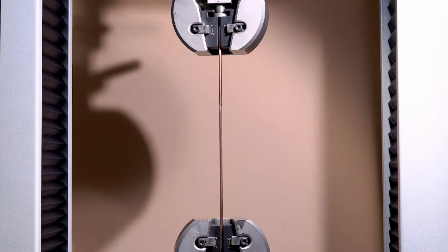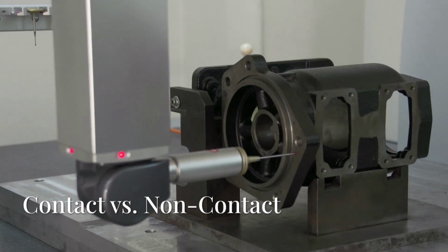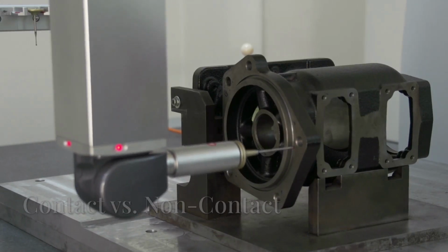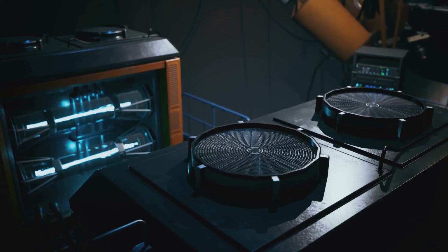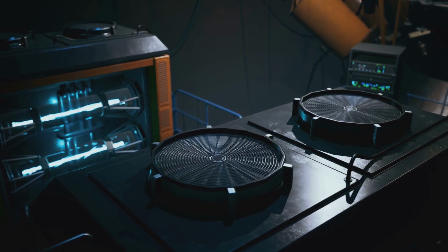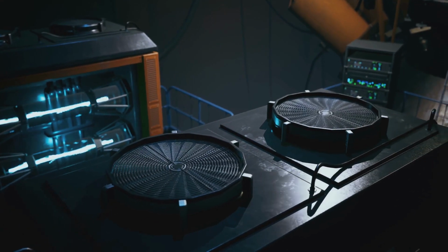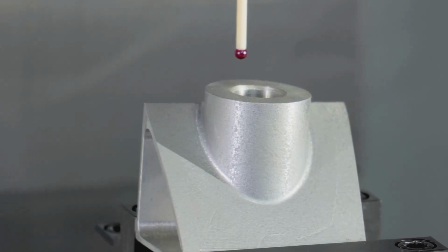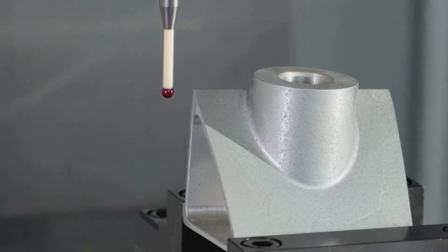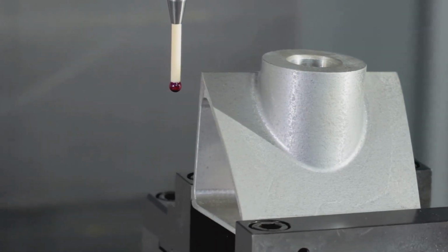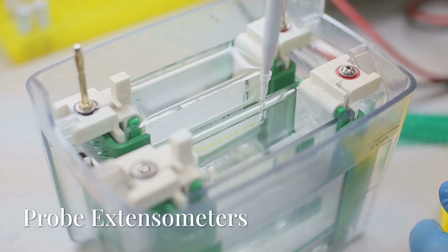Very thin specimens, such as foils, may be sensitive to clamping forces, while very small wire specimens do not provide enough visible area for reliable non-contact measurements. Depending on the application, extensometers are available in both contact and non-contact models. In the case of contact, the 2 most common forms are probe or magnet and rod extensometers.